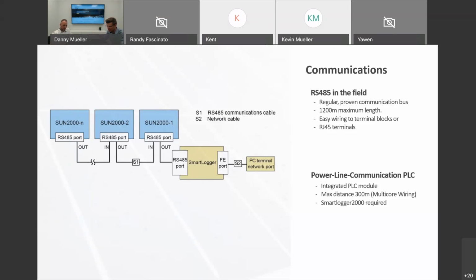Huawei also has a special PCB built into each inverter, which is a power line communication, which then modulates the communication signals and the data onto phase 1 and phase 2 of your three-phase system. And the Smart Logger 2000, which is the other end of the interface, will then take the data back off the AC, and you don't have to install any wire. There are limitations, of course, to that technique, because the PLC is restricted in length. If you have a multi-core conductor like a Teck cable or an SW, your capacitive coupling between the conductors is very good.